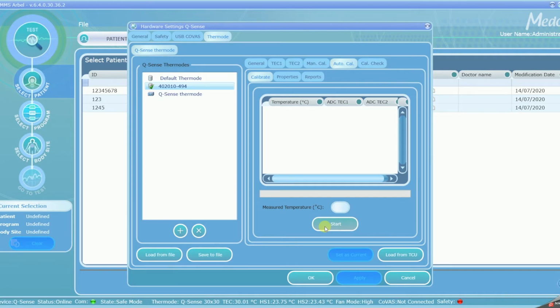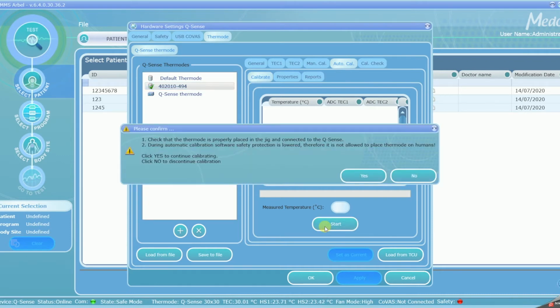When you start the calibration, make sure that the thermode doesn't touch anything but the sensor. During the calibration, safety measures are off, so the thermode can get to extreme temperatures for a long time. No body parts should touch the thermode at this time. Are you ready? Let's start. So this is just a confirmatory message. Make sure that the jig, thermode, and sensor are properly connected. And be aware of the safety precautions I've just mentioned to you.